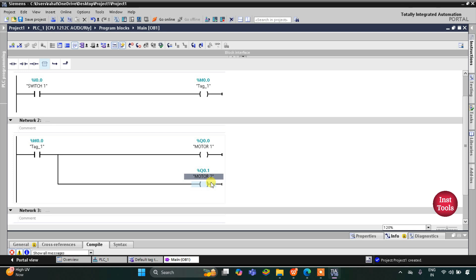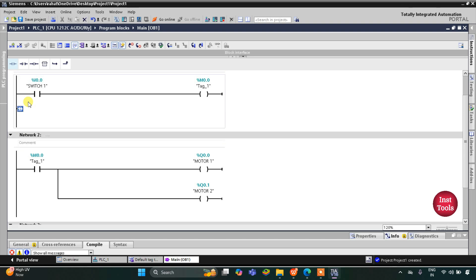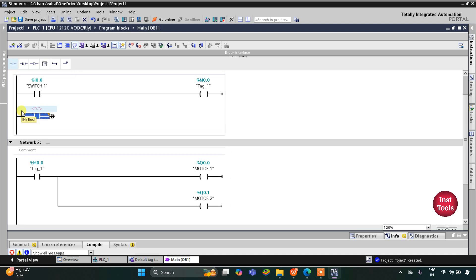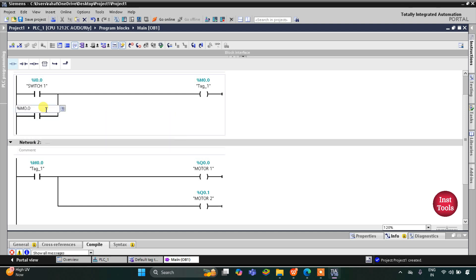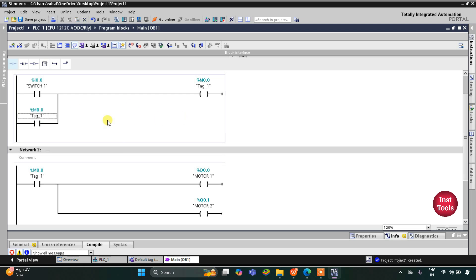But when switch 1 is turned off, M0.0 turns off which will turn off the motors. But after turning off switch 1, the motors should remain on. To achieve that we have to latch. So I will open the branch with Shift+F8, then insert a normally open contact with Shift+F2, and then close the branch.